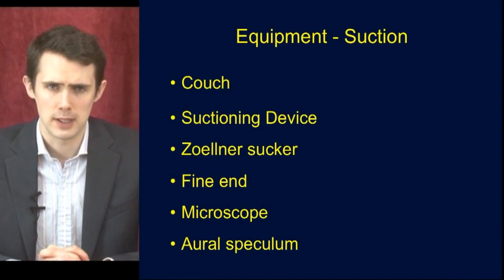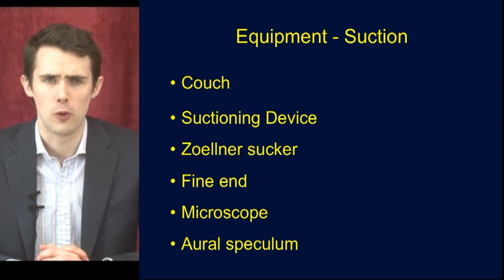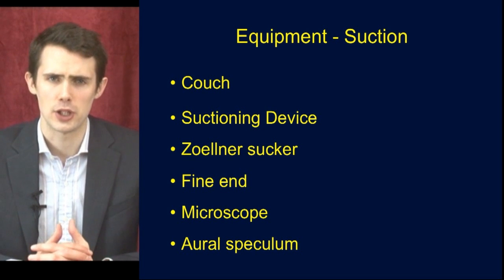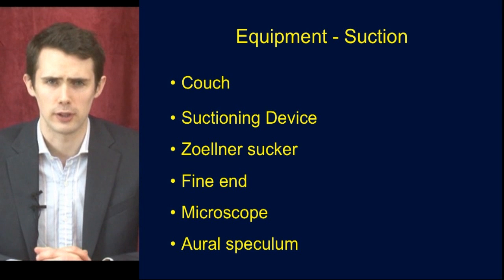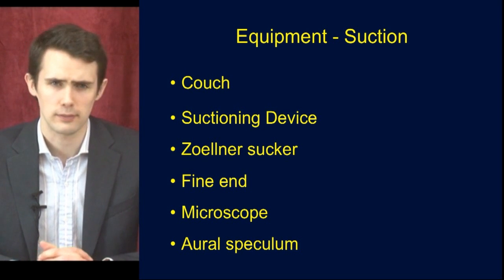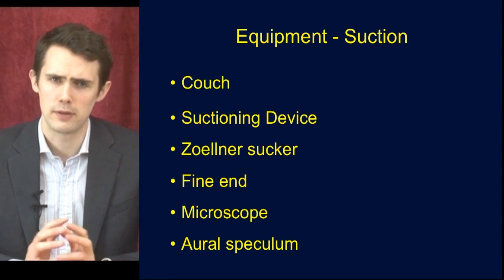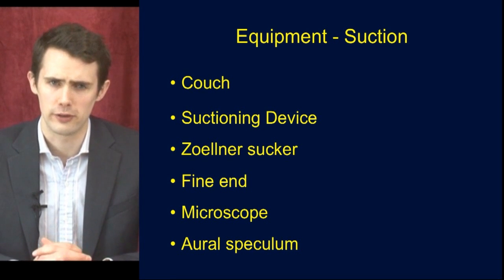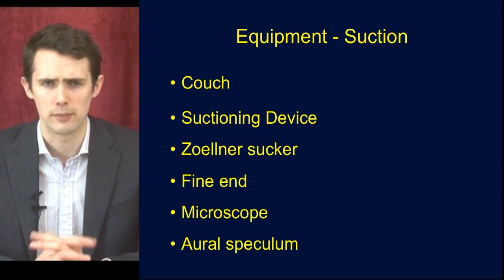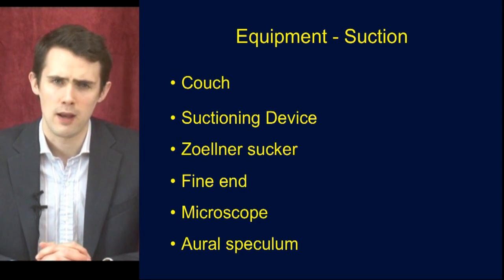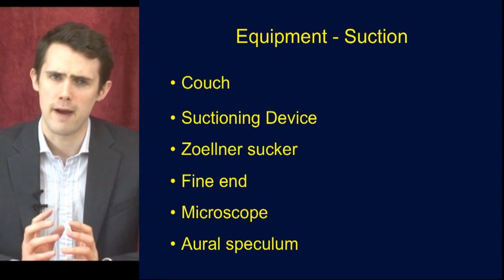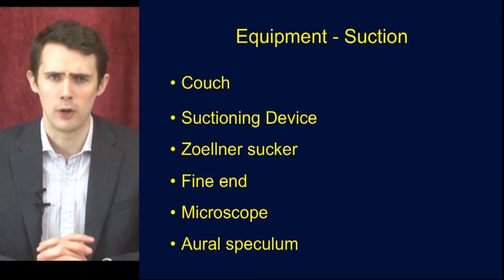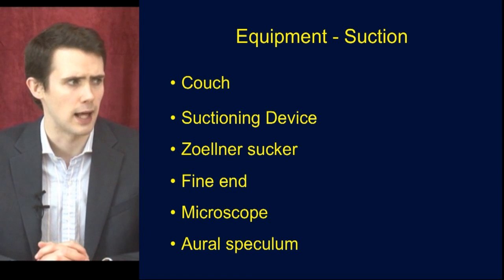A variety of equipment is required in order to perform microsuction. Traditionally, the procedure is performed using a couch to allow the patient to lie flat and still during the procedure. A suction unit will be required, and suction ends, usually a Zollner sucker, will be used. Zollner suckers come with attachments known as fine ends, which allow for more precise removing of wax from various parts of the tympanic membrane. A speculum is used to hold the very external cartilaginous part of the ear open and allow easy access to the ear canal.